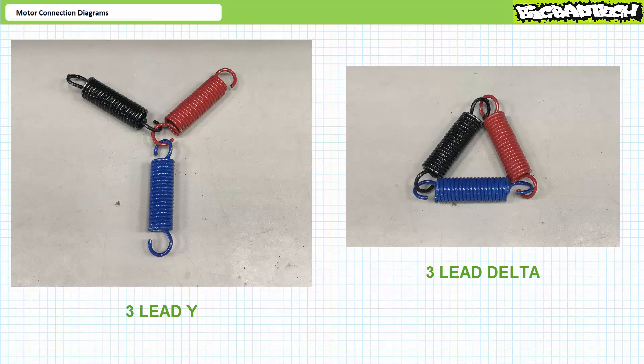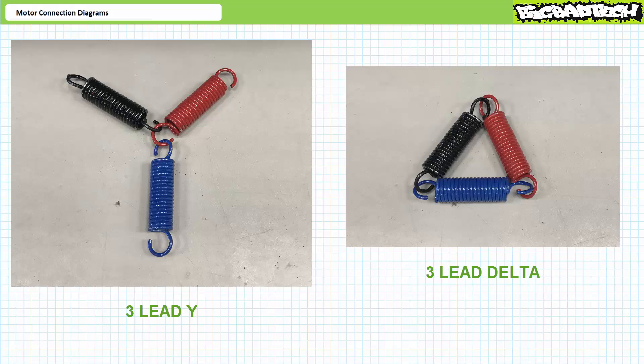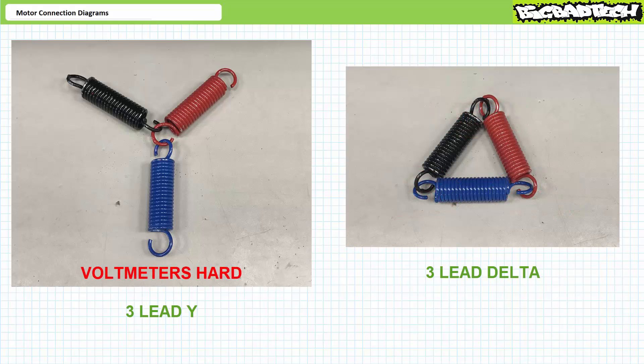Let me make an important observation about electrical instrumentation and three-phase AC motors. These are three-lead motors and one does not ordinarily have access to the internal connections and individual windings. This implies certain electrical properties might be easier to obtain depending upon electrical configuration, and others less so. A three-lead Y-configured motor typically hides the central node inside the motor, making it ordinarily impossible to measure voltage across an individual winding. Similarly, a three-lead delta-configured motor permanently bonds the windings together, so windings cannot ordinarily be broken apart to insert an ammeter in series and measure current through an individual winding.